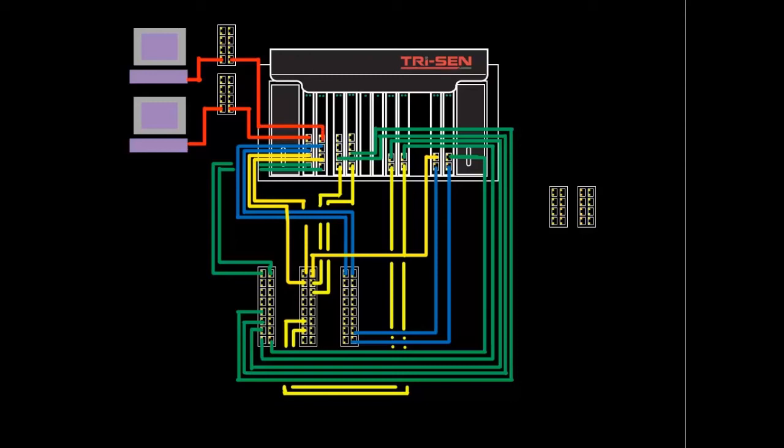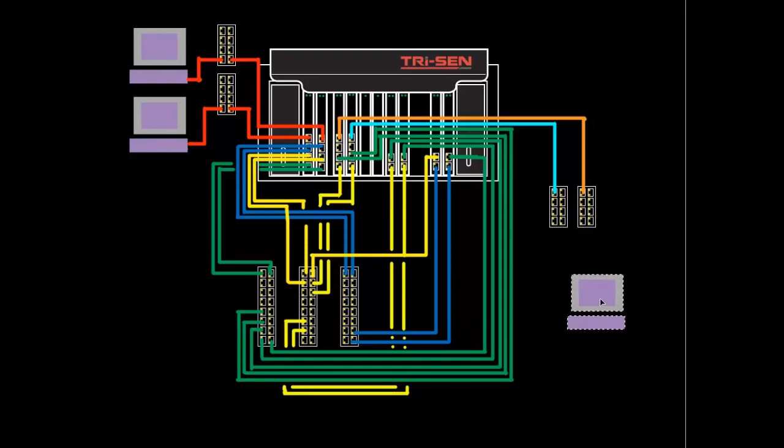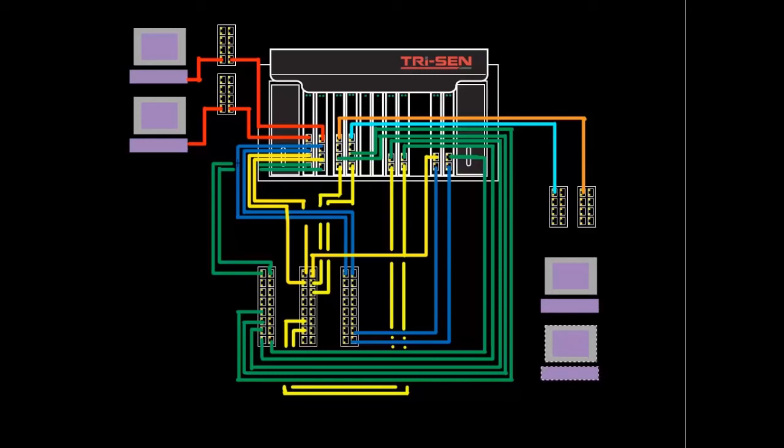Those other two switches over on the right side will be used to build a couple of DCS networks. So the top connector on each of the TCP IP boards we will have configured for Modbus slaves. So we put in two independent slave networks. We need something to represent the DCS so we'll just use a couple of these PC symbols. And then each of those two computers will be wired up to those two switches.